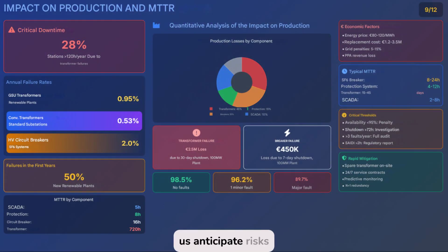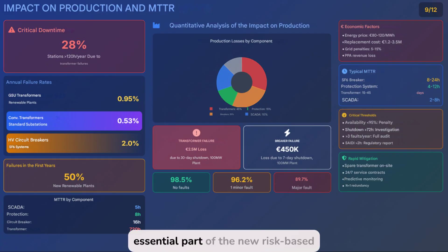Reliability curves help us anticipate risks and make more informed investment decisions. If we reach 98.5%, we can operate without breakdowns. At 96.2%, we will likely face a minor breakdown. But when we drop to 89.7%, the risk of a major breakdown with critical consequences skyrockets. These curves, combined with component-specific criticality analysis, are an essential part of the new risk-based approach that is setting the trend in electrical asset management.